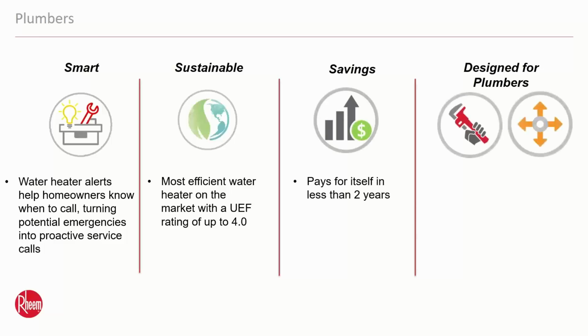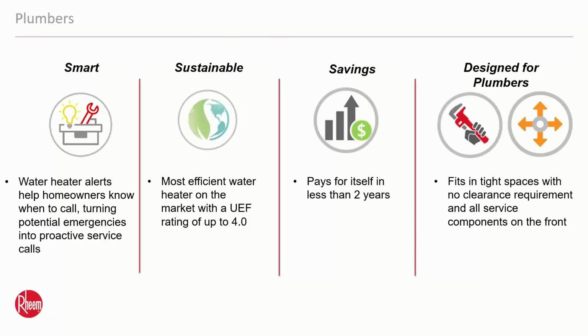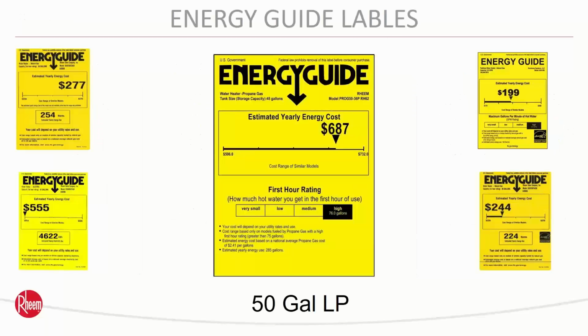through its savings. And it's designed for plumbers. It'll fit in tight spaces. All the serviceable components are on the front of the unit, so you don't have to worry about getting around behind it. The other thing is, you do not have to work on the compressor. Our unit's a sealed system, so if anything goes wrong with the heat pump part on the top, you replace the whole heater. You don't have to go in there and recharge it or work on the compressor itself.